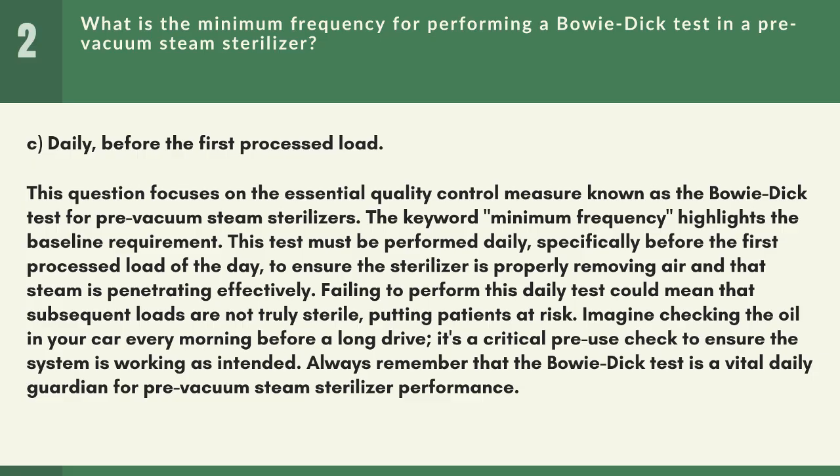Failing to perform this daily test could mean that subsequent loads are not truly sterile, putting patients at risk. Imagine checking the oil in your car every morning before a long drive. It's a critical pre-use check to ensure the system is working as intended. Always remember that the Bowie-Dick test is a vital daily guardian for pre-vacuum steam sterilizer performance.